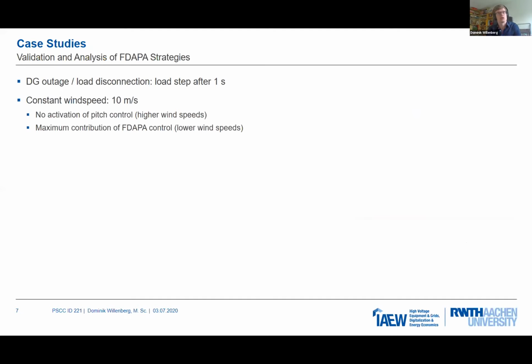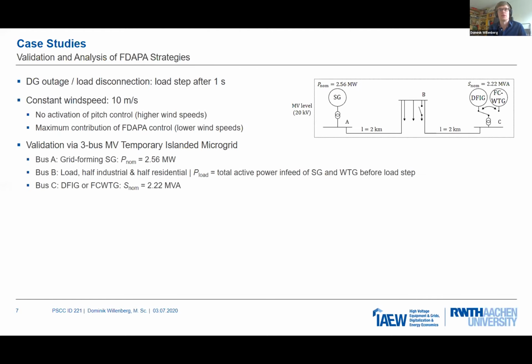Generally, a DG outage or load disconnection is simulated, which is equal to a load step after 1 second. Moreover, a constant wind speed of 10 meters per second is assumed, so that no activation of the pitch control in case of higher wind speed needs to be performed, and the evaluation of the maximum contribution of the different control approaches is possible, which would of course not be possible in case of lower wind speeds.